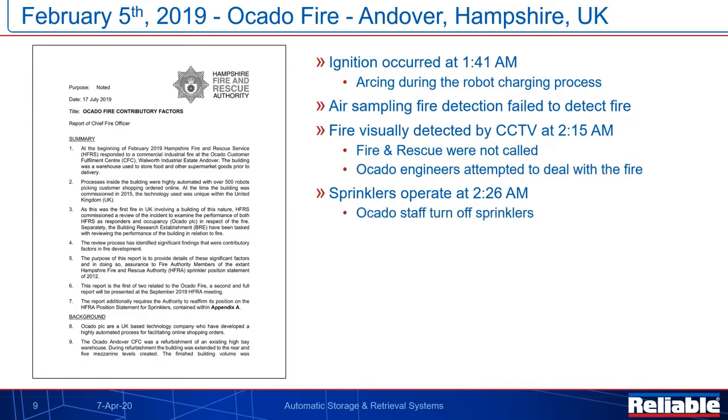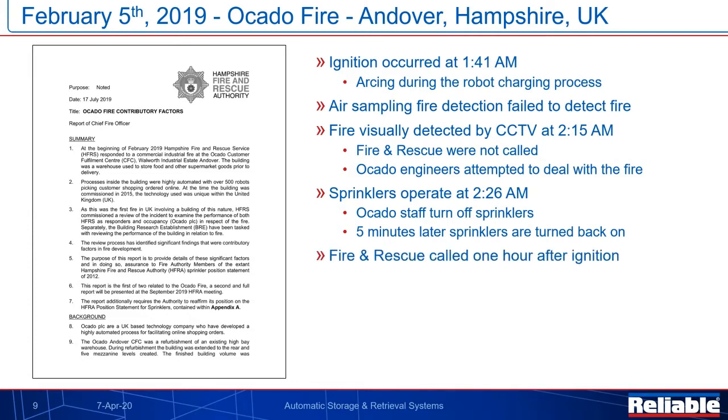Inexplicably, the Ocado staff turned the sprinklers off. Whether they thought this fire was controlled, contained, or out, or whether they were trying to save some of the grocery produce, it's not clear. But turning the sprinklers off before the fire is extinguished is not the best thing. So 5 minutes later, they decided that they should turn them back on. And it was not until an hour after ignition that fire and rescue was finally notified.